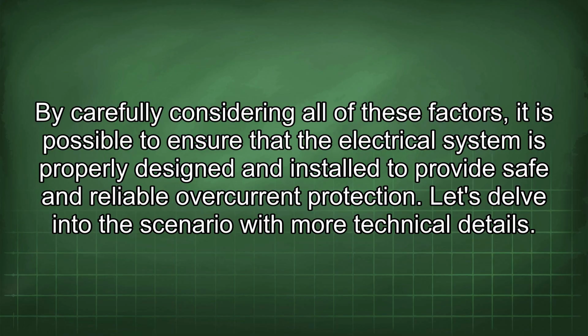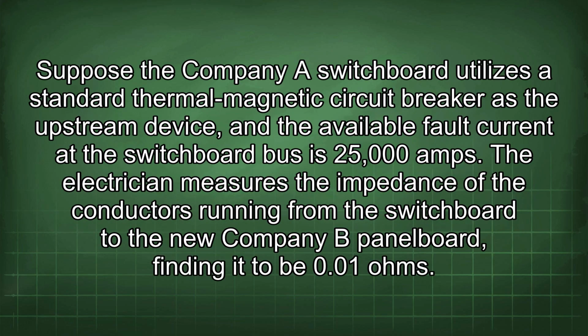Let's delve into the scenario with more technical details. Suppose the Company A switchboard utilizes a standard thermal-magnetic circuit breaker as the upstream device, and the available fault current at the switchboard bus is 25,000 amps. The electrician measures the impedance of the conductors running from the switchboard to the new company B panel board, finding it to be 0.01 ohms.